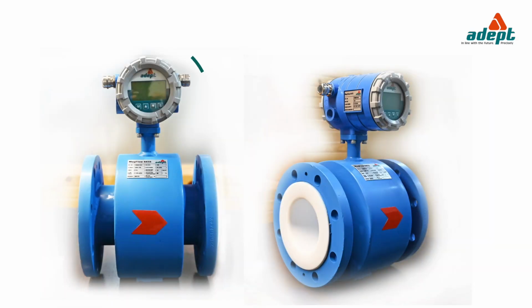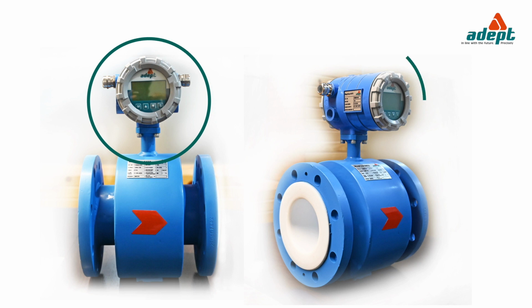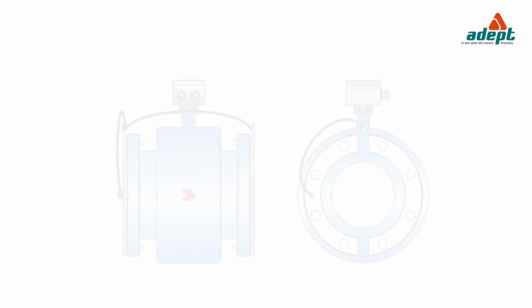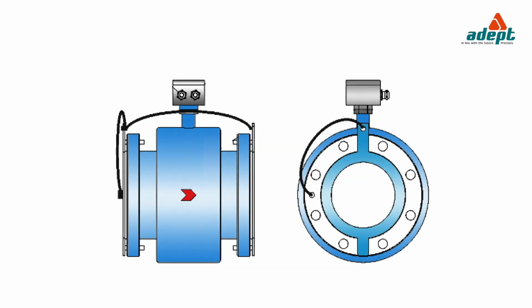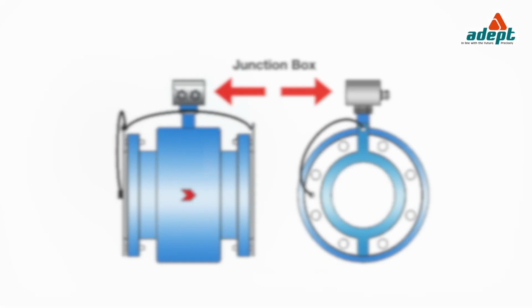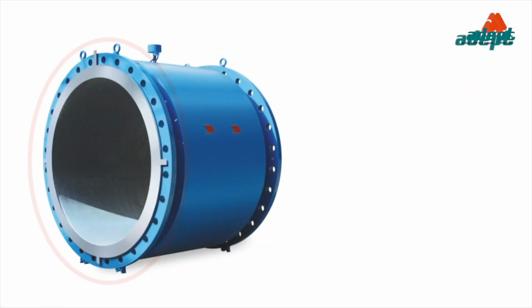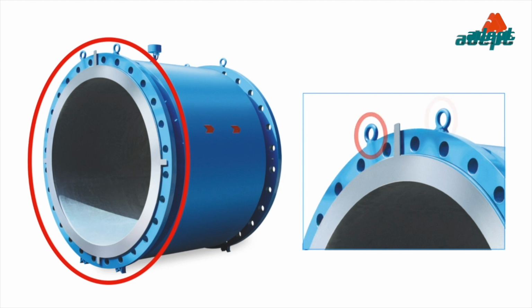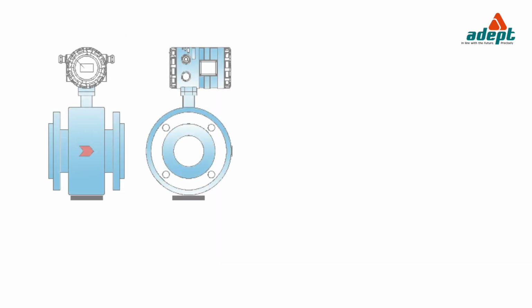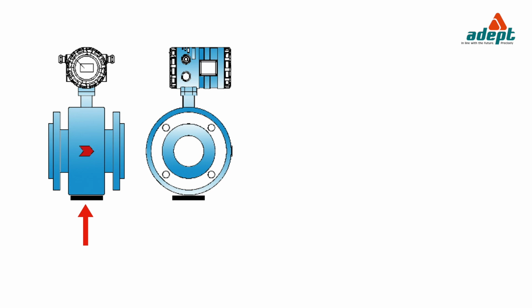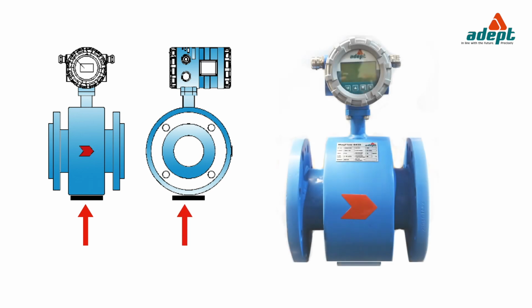Important handling instructions. Do not lift the flow meter by the top mounted transmitter in case of an integral type flow meter. Do not lift the flow tube by the top mounted junction box in case of a remote type flow meter. Do not lift flow tube by its casing. Always lift the flow meter of size DN200 and above using the eye bolts. Always rest the flow meter only in its upright position on the pedestals provided and not on its casing.